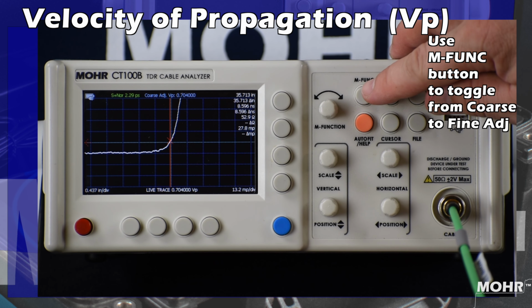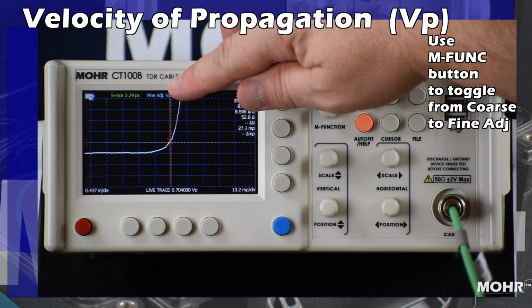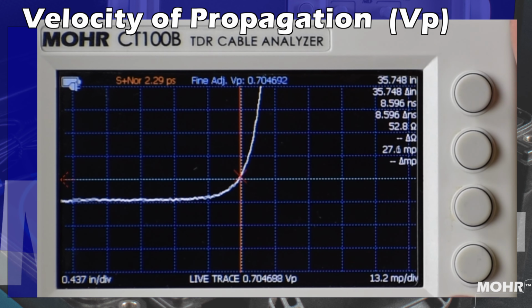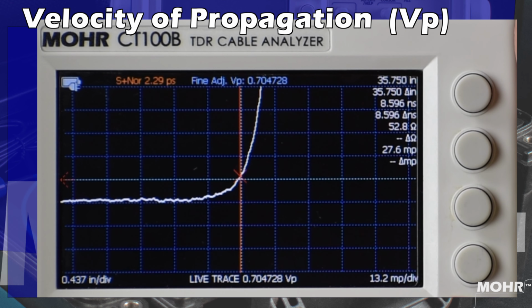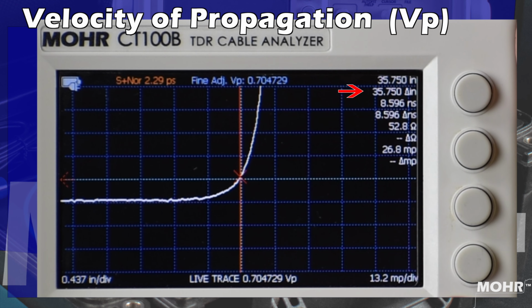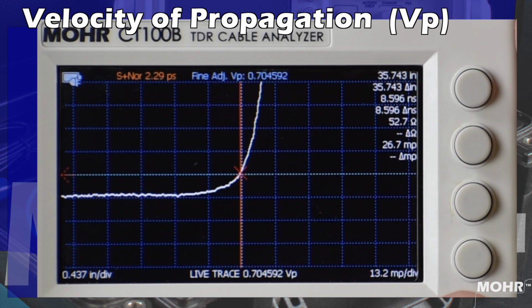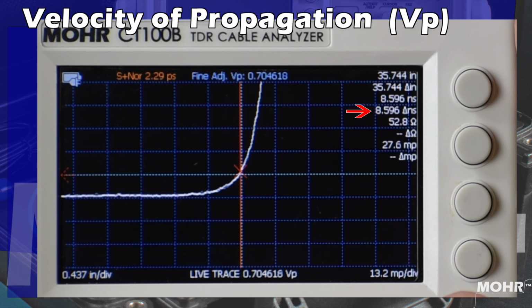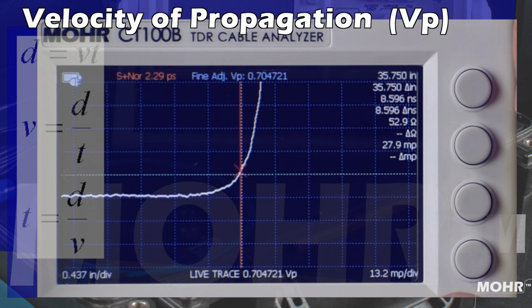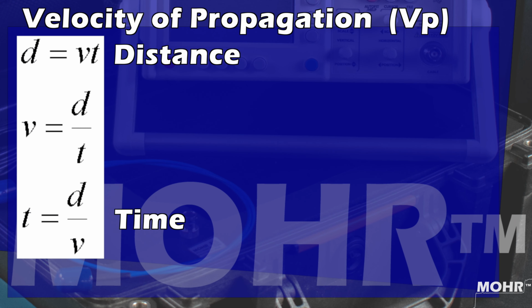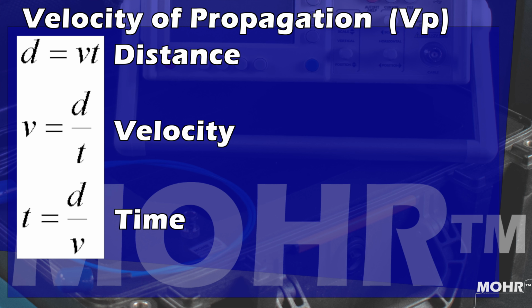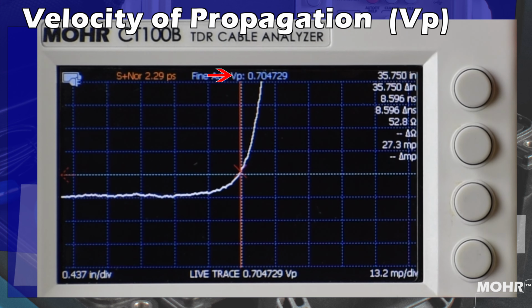then the M function button to toggle to fine, and adjust the VP till the measurement shows the predetermined length of 35 3/4 inches. As I'm adjusting, notice that the time stays constant. You're not adjusting the length of the cable, you're adjusting the variable to make the equation match what has already been physically measured.